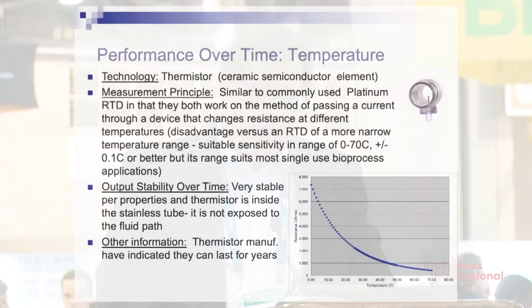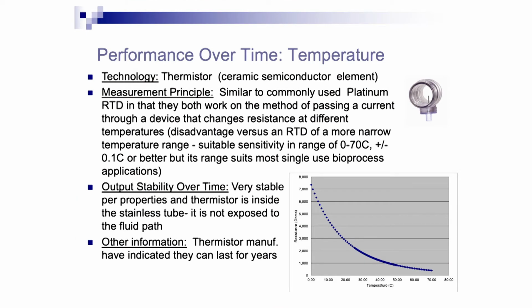The temperature element in ours is called a thermistor. A lot of people are familiar with an RTD, which is a precious metal junction. A thermistor is a silicone junction. It performs very similarly and has a good response time. It just has a much narrower range, but that's fine for bioprocess applications. And it's been documented to be extremely stable over time because it doesn't really undergo any changes.